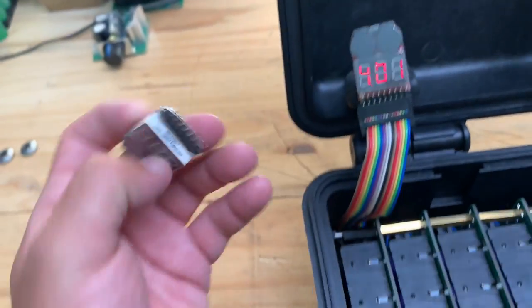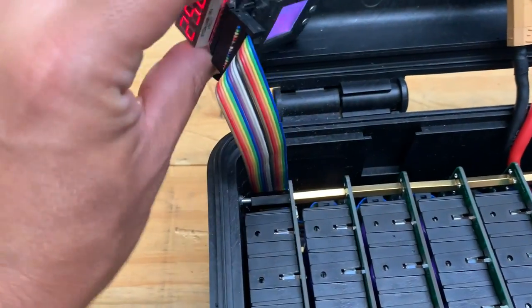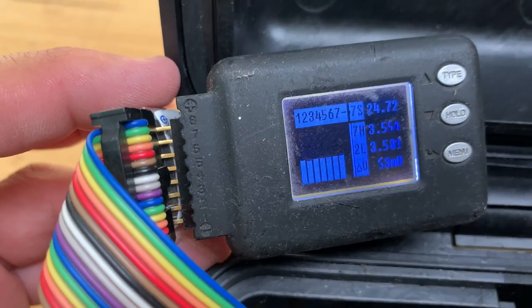It's set to 2.7 volts. If it hits 2.7 volts it'll start the alarm. I did this with another unit — I'm ruling out that it's just one bad unit. See, the alarm is going off — that means one cell must be at 2.7. But no, none of the cells are at 2.7. In fact, let's look at what this thing is actually reporting.